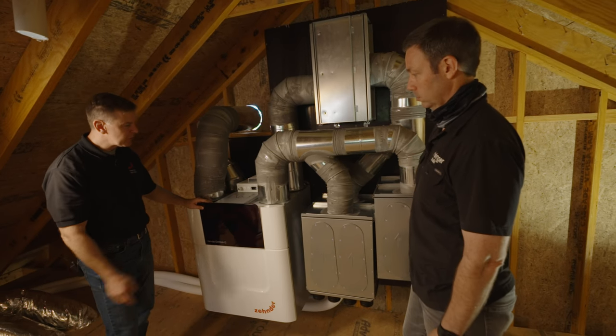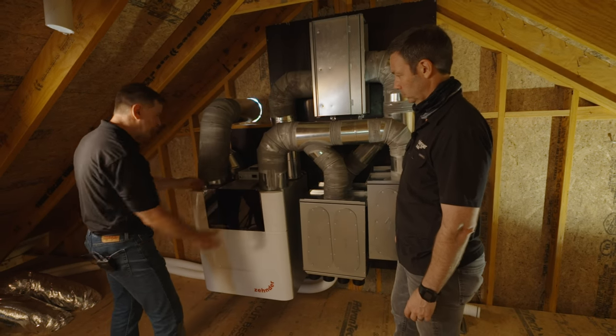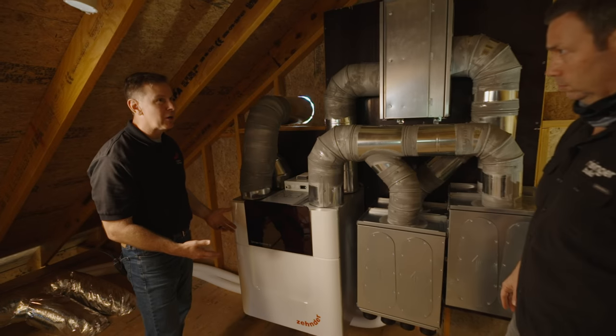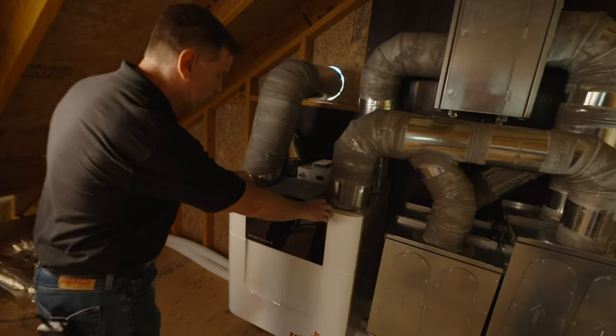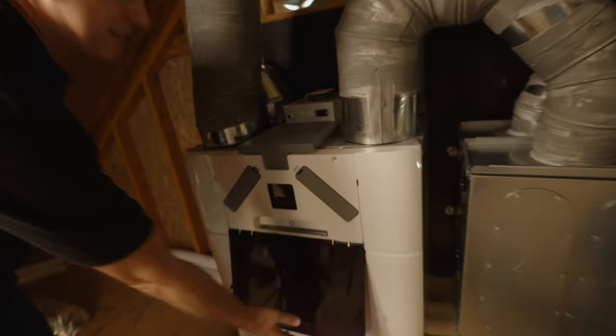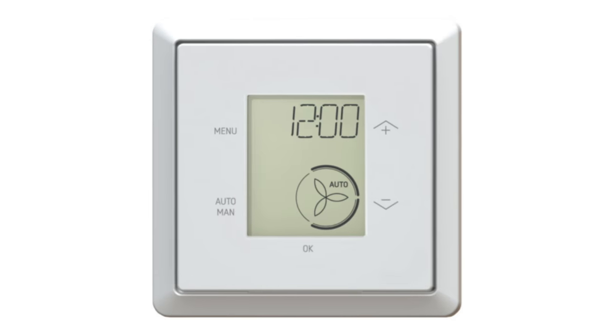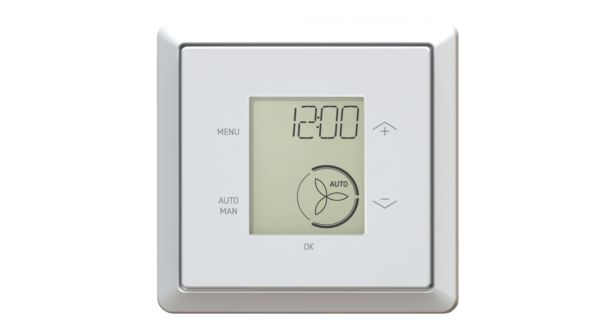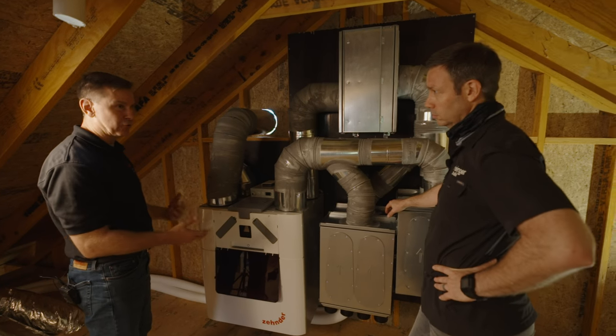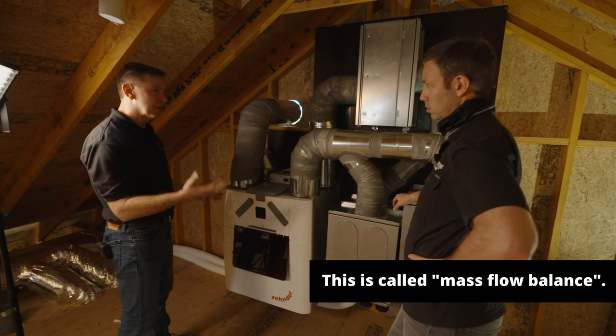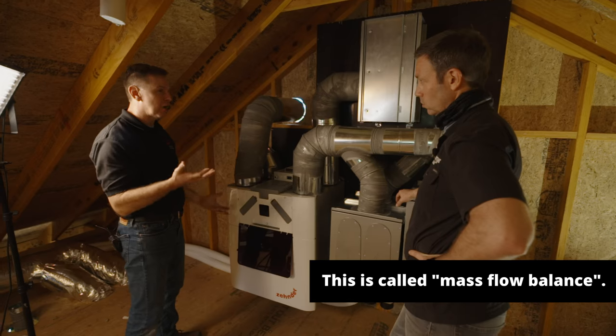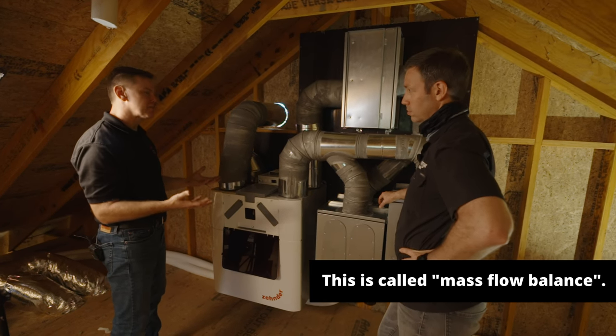Great, sure, okay, well let's start with the guts first. The Q600 is a really smart ERV. It's a self-balancing unit, so the controls are constantly monitoring the air temperature. It knows the altitude you're at because you plug that in during commissioning, and so it can calculate, based on density, how much air is actually flowing through it. It will adjust the supply fan and the exhaust fan independently to constantly maintain balance.